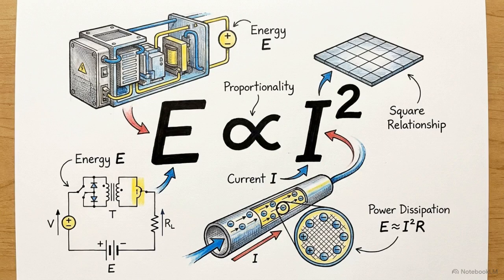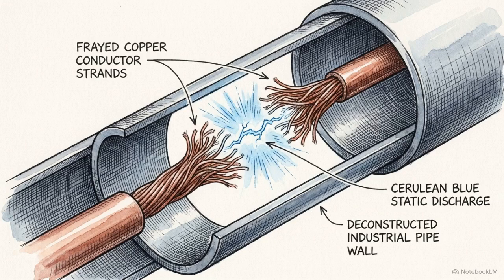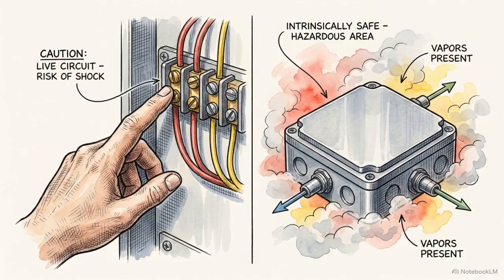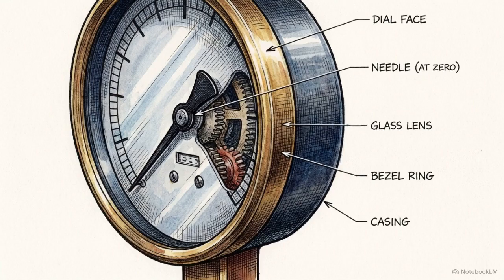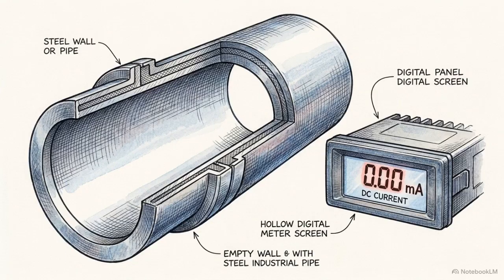The energy required to ignite an explosive gas is proportional to the square of the current. By limiting the maximum flow, the total energy in the loop stays so low that even a dead short circuit cannot generate a hot enough spark to trigger an explosion. The 20 milliamp ceiling is an engineered boundary determined by the physics of human safety and combustion. Looking at the bottom of the scale, the intuitive assumption is to start at 0. It seems logical that 0 pressure in a pipe should equate to 0 milliamps of signal.